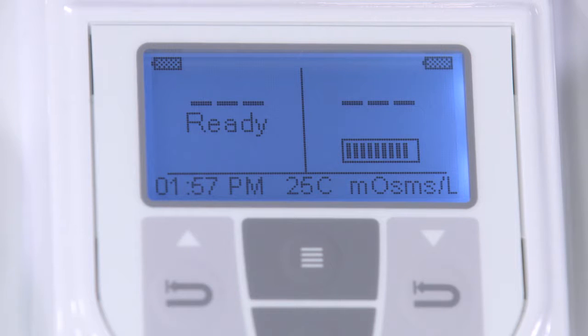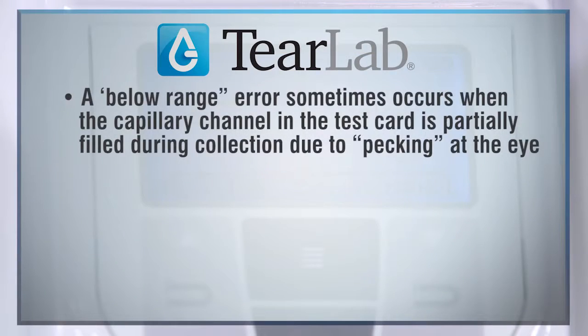You may also see a below-range error on the TearLab reader after performing a patient test. A below-range error sometimes occurs when the capillary channel in the test card is partially filled during the collection due to pecking at the eye.